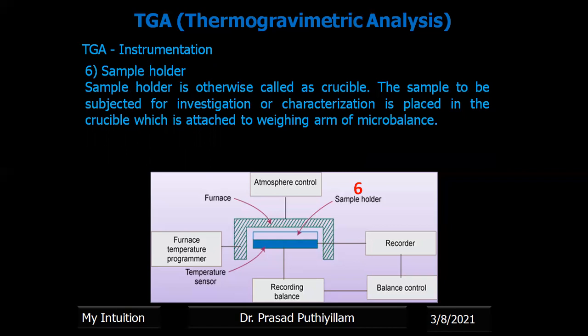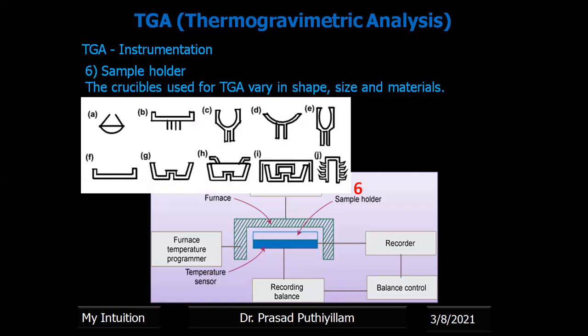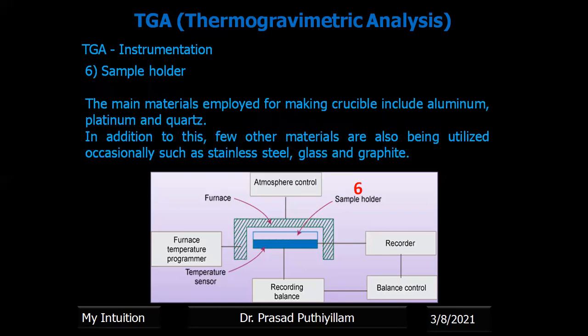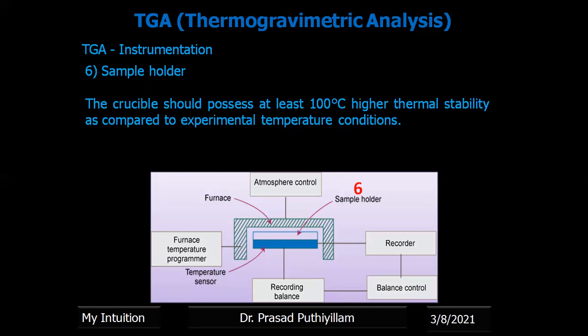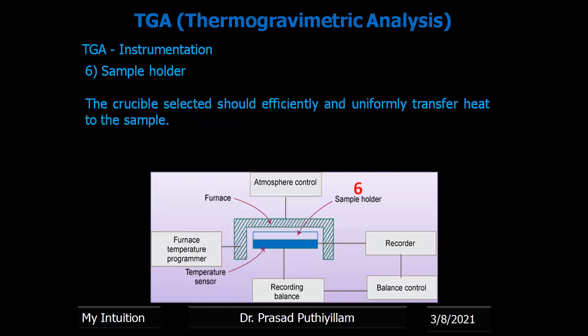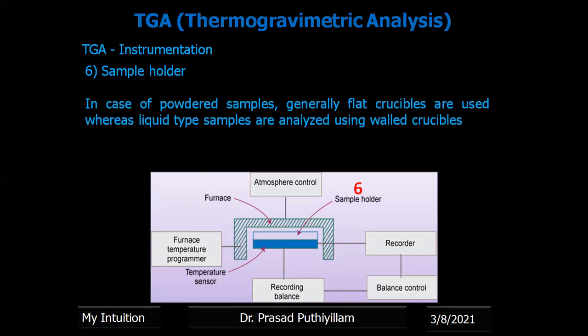The sixth component is the sample holder, which is a crucible. The sample is placed in the crucible, which is attached to the weighing arm of the balance. Different shapes, sizes and materials are used for crucibles. Main materials include aluminium, platinum and quartz; stainless steel, glass and graphite are also used. The crucible should have at least 100 degrees Celsius higher thermal stability than the experimental temperature. In the case of powder samples, flat crucibles are used; for liquid type samples, walled crucibles are used.